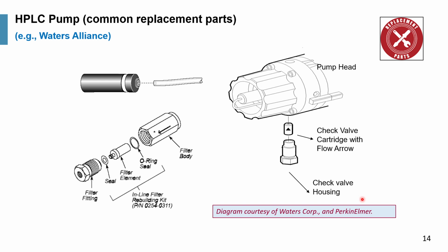So here are some of the common parts in a little more detail: replacing the Waters Alliance check valve, most likely in the mobile phase A pump, with a new check valve cartridge pointed in the upright direction. Here is the sinker. It's a 10 micron stainless steel filter disc, which can be easily replaced. And here is an inline filter.